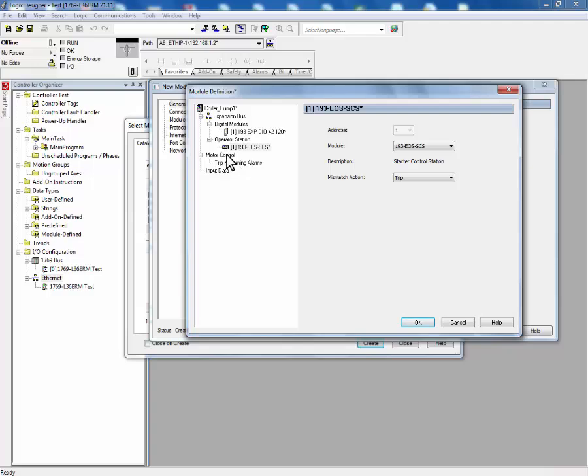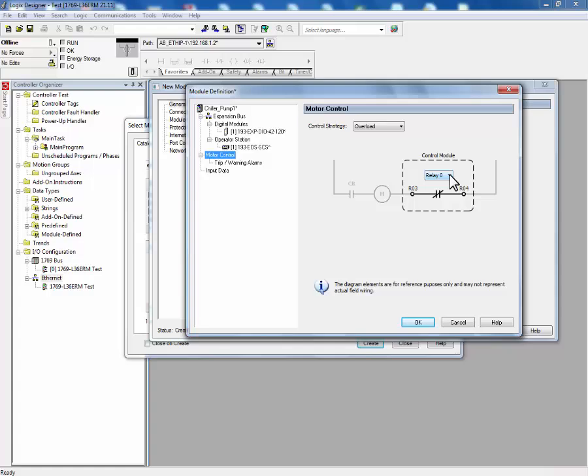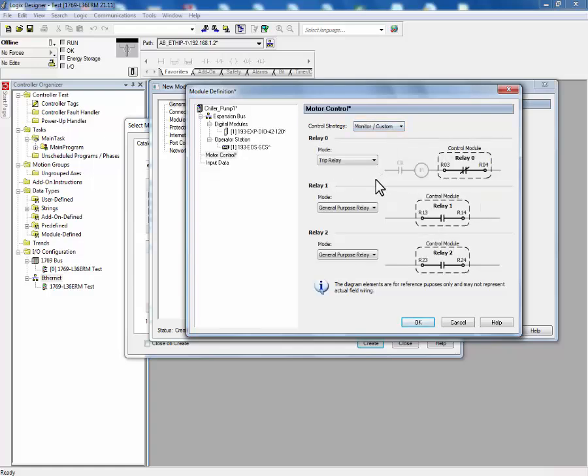Next, we'll define how we want the motor control algorithm to operate. Today, we have a couple control strategies to choose from. We can either choose a traditional overload with a normally closed relay or we can choose a monitor mode or custom mode. For this example, we'll use custom mode and we will use relay 0 as a combination control and trip relay.